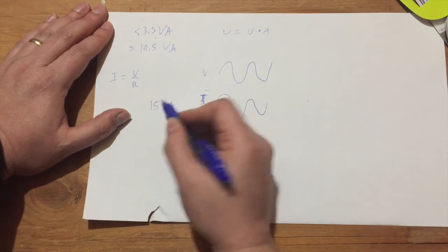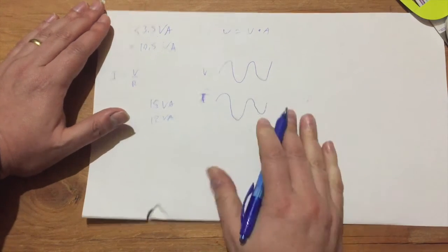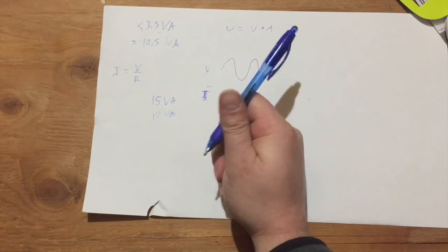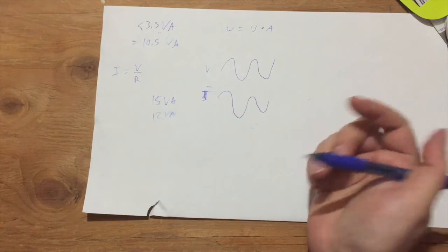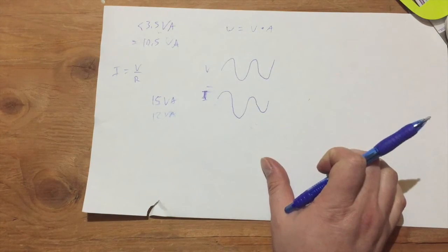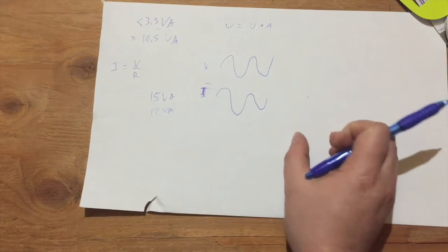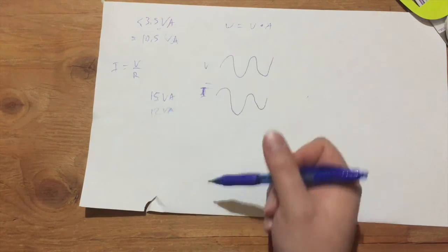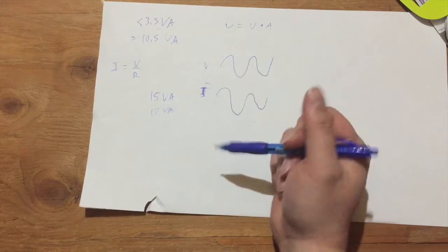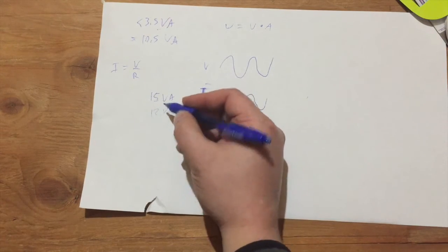So 80% of this 15 VA, let's say, just based on these amperage ratings, would be 12 VA, which should be available for use by thermostats. So actually, that seems like it should be fine. We've got a little bit of headroom. Now, if you've got a three-zone controller, three or less, you're fine. In my case, I've got a four-zone controller, but I'm only running three thermostats, so that should be fine, assuming that the water heater doesn't draw much, which I happen to know it doesn't. So that should be fine.